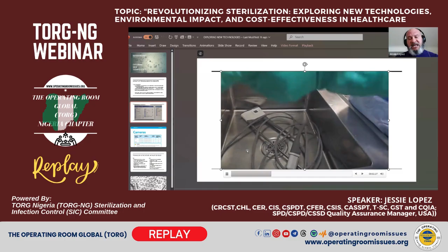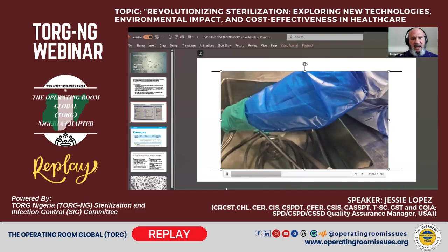It's important that you have pressurized water to flush out those soils and detergent. The next part of this IFU tells me to use pressurized water for the distal tip of the device, because the distal tip has some flexible components and joints and a honeycomb pattern that can have trapped soils, and it's very difficult to get a cleaning tool in there to really scrub off those soils.